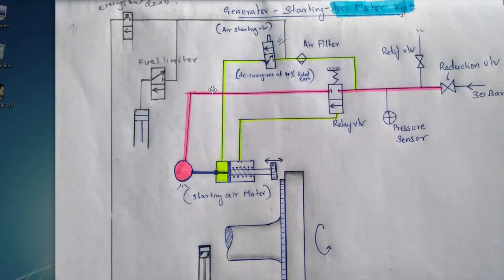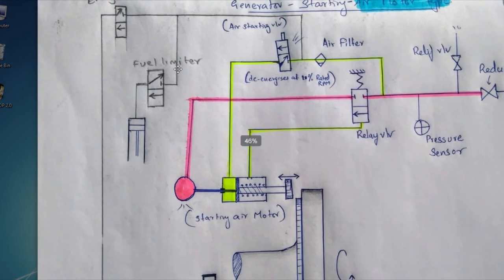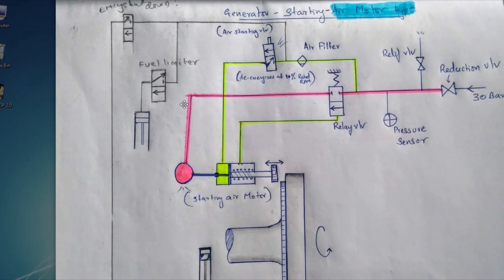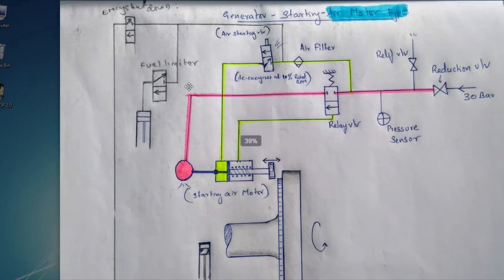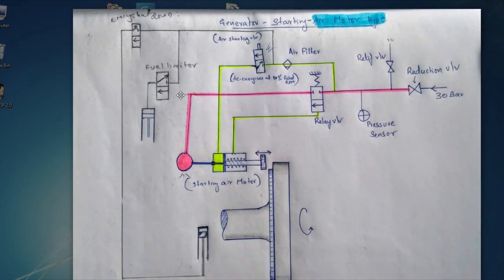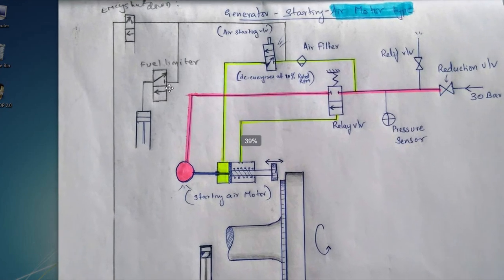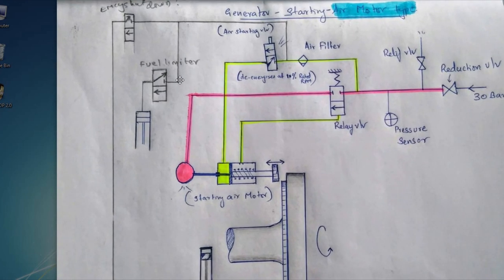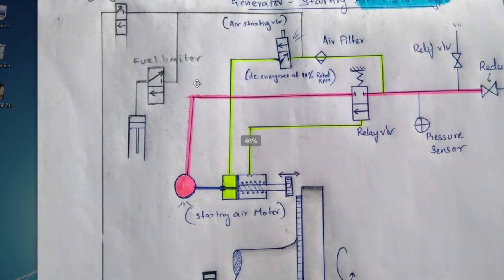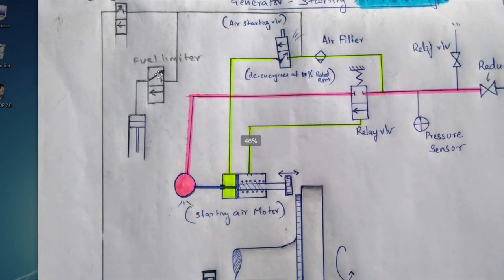I need to mention one more thing in this, is that this is the fuel limiter. At the time of starting, we should not allow the fuel rack to go 100% in. It will cause black smoke at the time of starting. So with this fuel limiter, what it does is it only allows 30 to 35% of the fuel rack to go in. Thus reducing the black smoke.